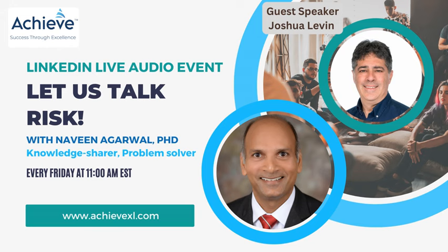I totally agree with you, Josh. And what I have kind of practiced is make the SOP general in the sense that it must require evaluation of hazards, harms, and severities at the product level. And then you create a standard record of harms, hazards, and severities that you can use after updating each time according to the product. And that record gets referenced into your risk management. So I think you don't want to change your SOP too frequently, right? I think that would not work very well. So now, one thing some companies do, I'll say, is they will have a standard risk acceptability table in the SOP. And then in the risk management plan, if you're just going to use the standard risk acceptability table, you can do that. Because that shouldn't change too much from device to device.